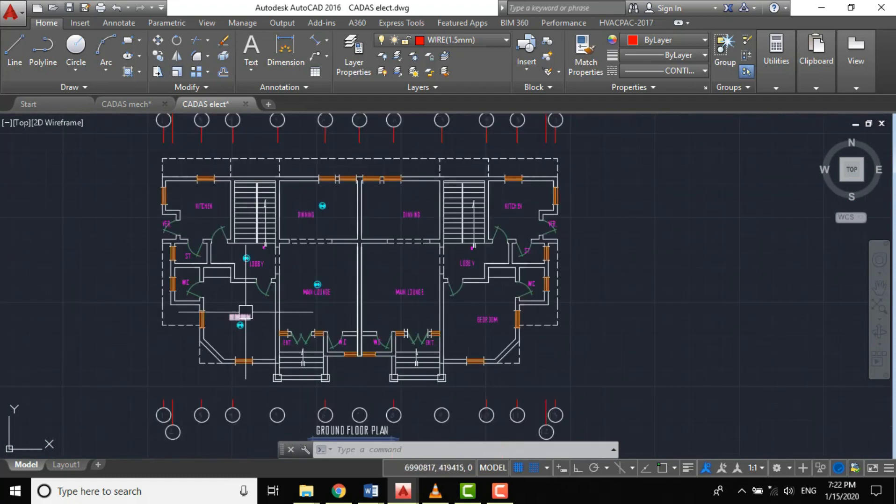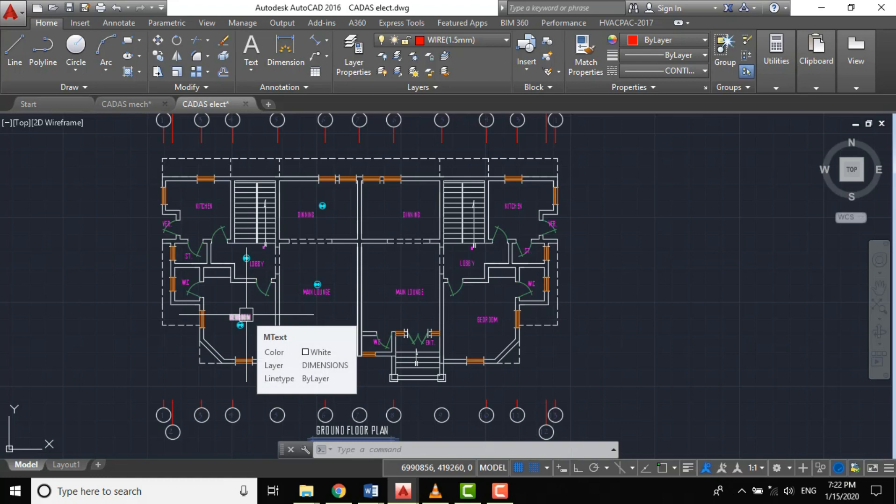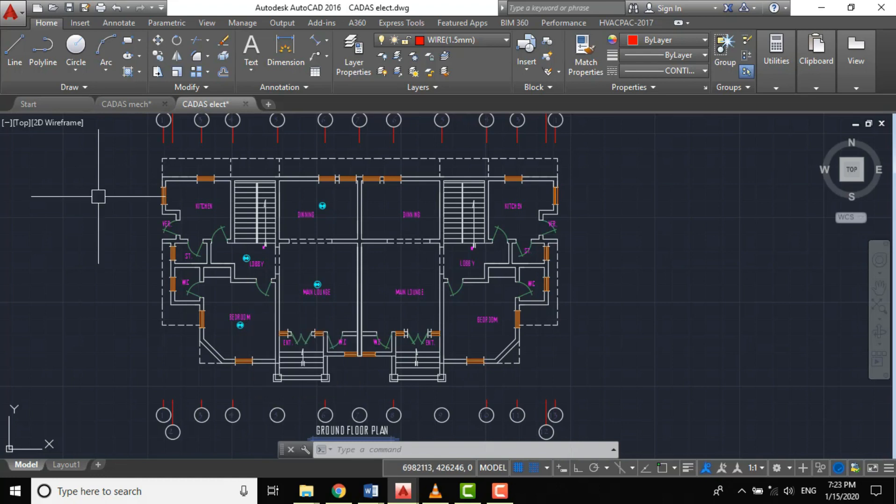Basically, every floor in a building must have its own zone unless the total floor area is less than 300 meter square.